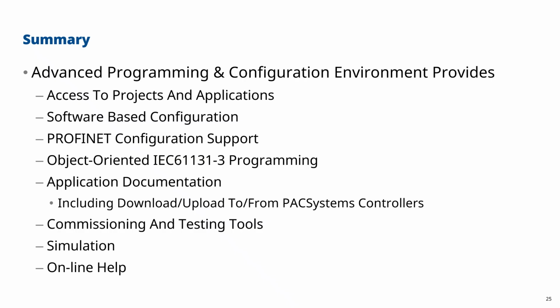For everything else, everything is software-based configuration. Even for Profinet, with that Profinet configuration support, that includes the capability to configure via the GSDML file, and that includes the configuration for all of the I/O modules within a configurable Profinet I/O device. So for example, with an analog module, you can go in and set the individual channel setups, is it voltage or current? And then for each channel, you can set the actual range, for example, again, is it 0 to 20 or 4 to 20. So all of that is configured through PAC Machine Edition.